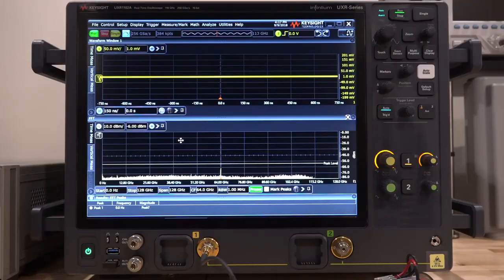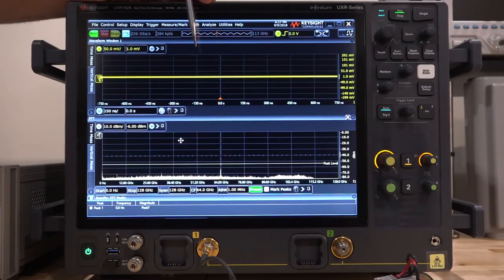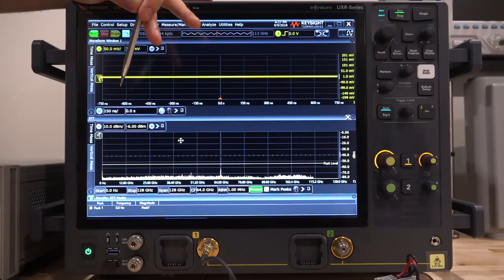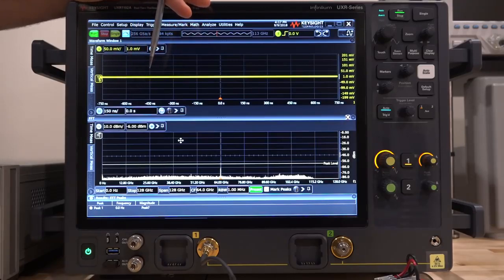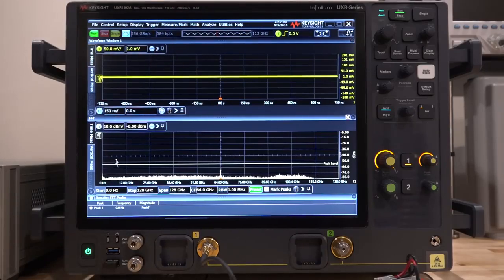So let's take a look at the output spectrum that this instrument produces. Right now I have channel 1 set to full bandwidth, 113 gigahertz, at a full sample rate, 384,000 points and 150 nanoseconds per division. This allows me to compute the FFT, and the FFT will span anywhere from 0 hertz all the way up to 128 gigahertz at a resolution bandwidth of 1 megahertz. We can in fact look at that just to make sure the resolution bandwidth is 1 megahertz. There it is, 1 megahertz resolution bandwidth.